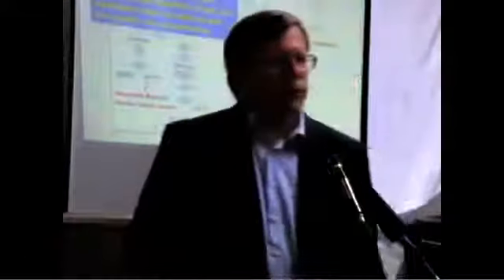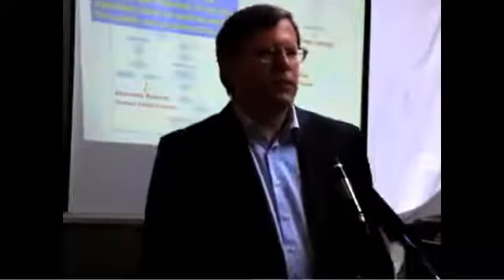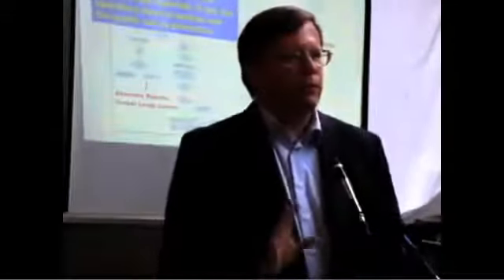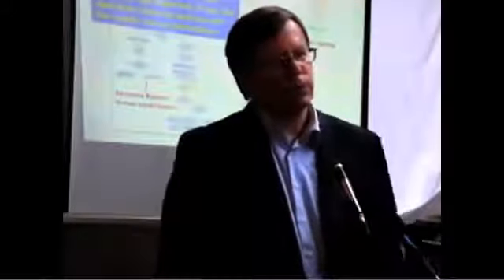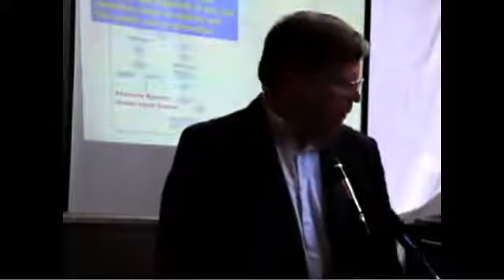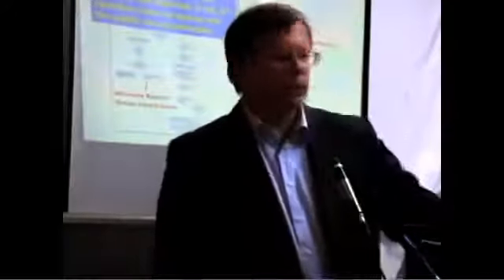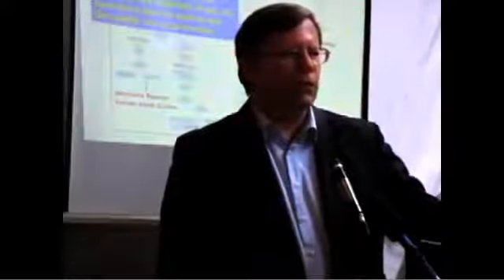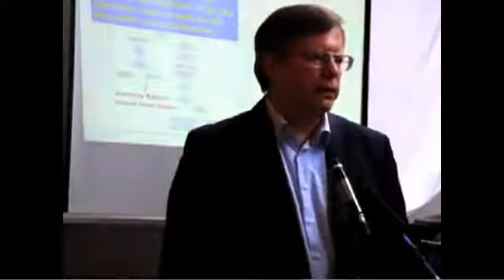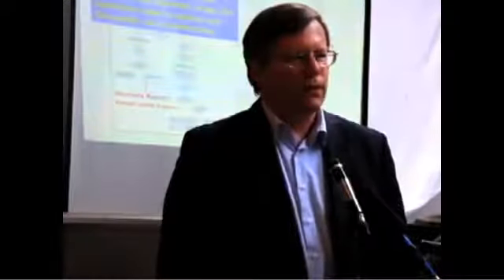But that really only works when the accidents follow the script. All of this is based on the assumption that we get power back within 4 hours, because that's what we assumed. So therefore, by fiat, power is restored within 4 hours. In Japan, they assumed it was restored within 8 hours. So if the accident doesn't follow the script, if the power doesn't come back when it's assumed to, the operators have no guidance at all on what to do.